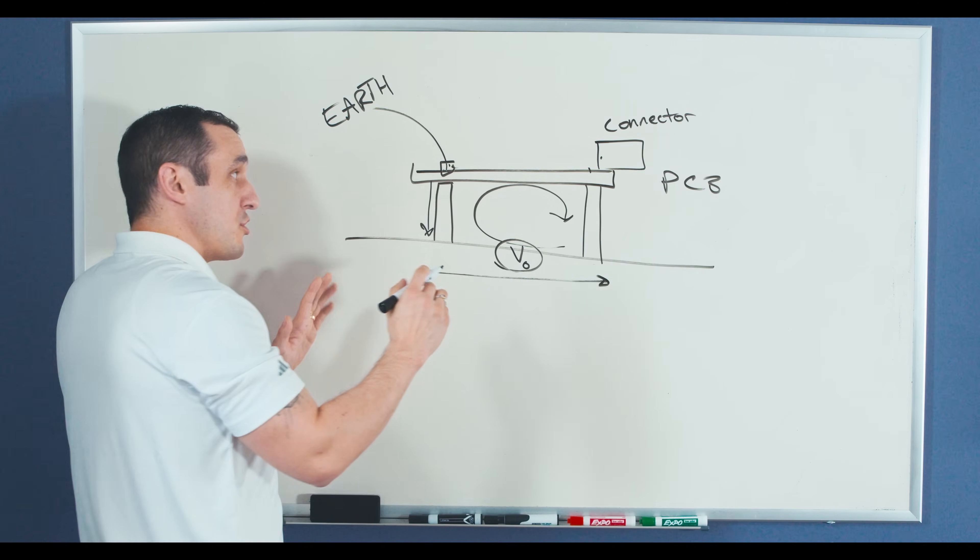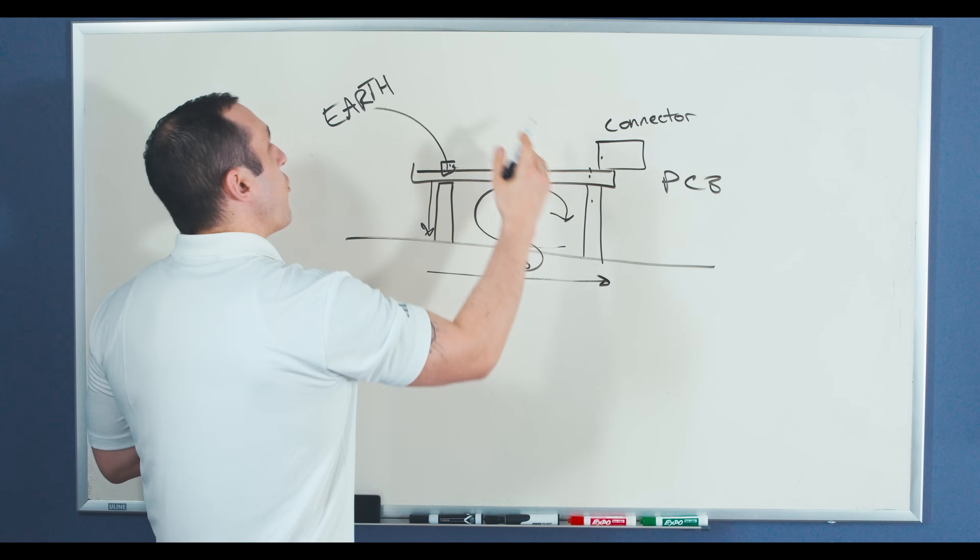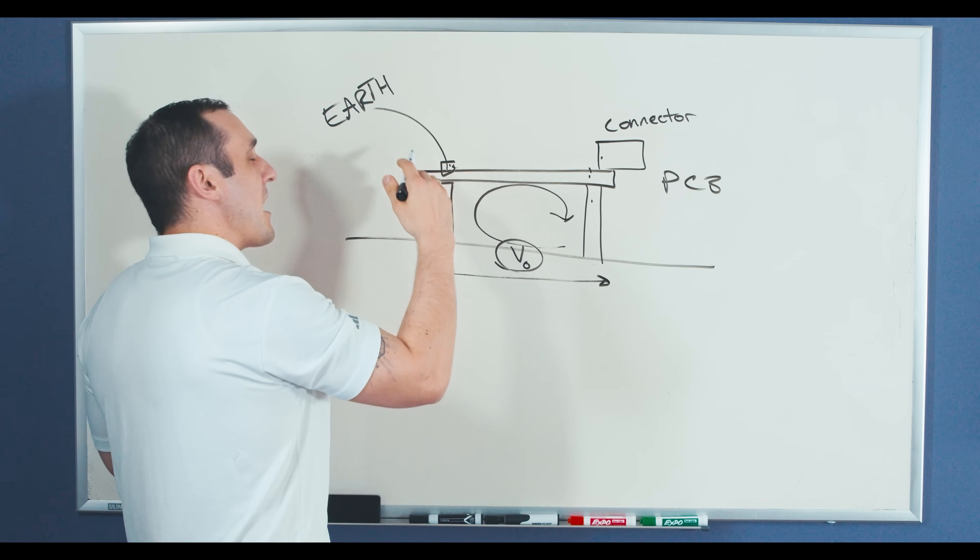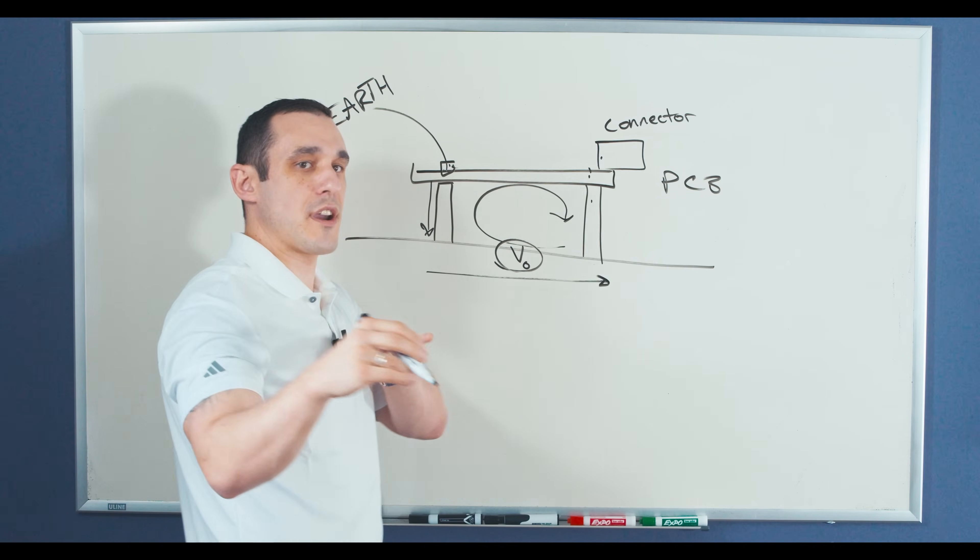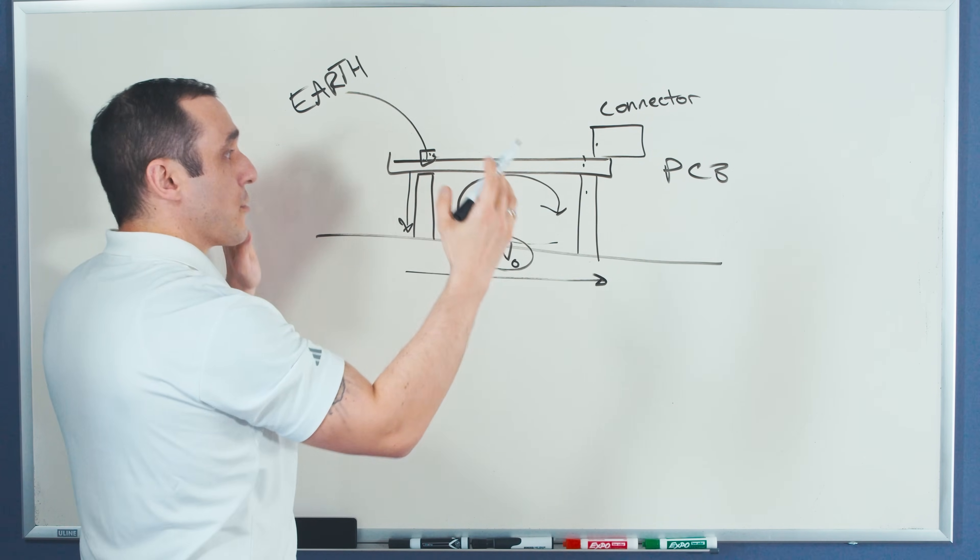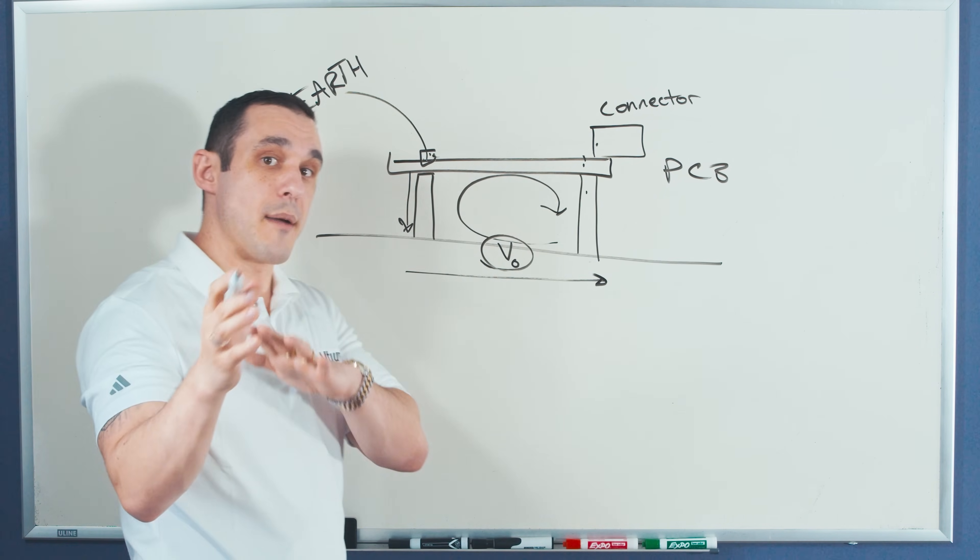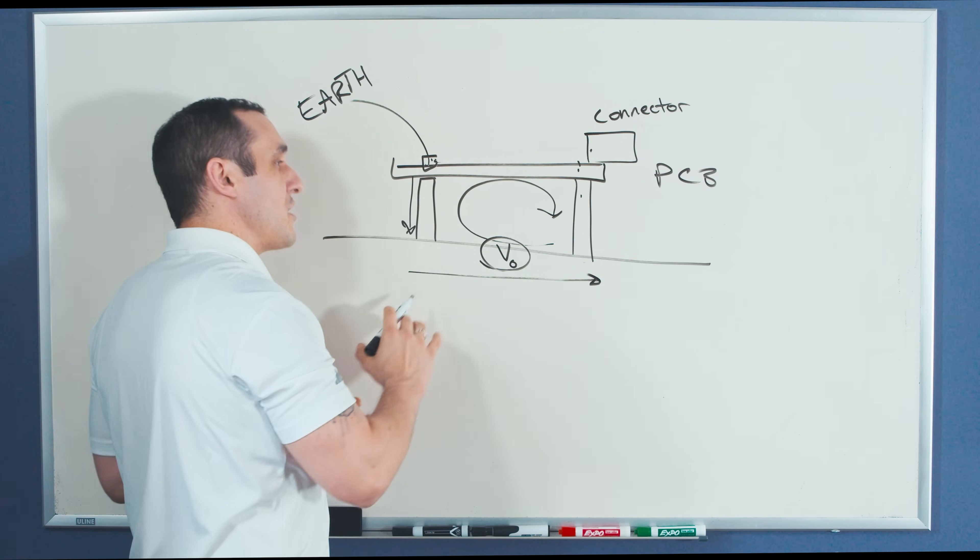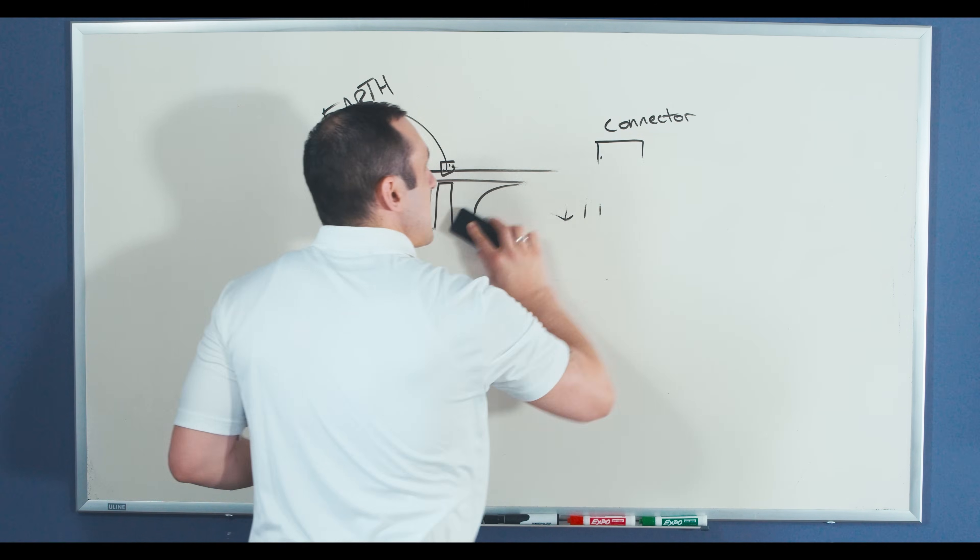For example, if you have a connector here with some shielding on the connector housing, all of that can be used to then access the safety ground. But again, because you're not putting a direct connection from here over to here, you're actually not creating a ground loop, even in this case where you have this connection among these different elements in a metalized enclosure. I think here the thing that you don't want to do is you don't want to connect your system ground over to your chassis ground when you have this earth connection. The issue here is that you could then run a current through that earth connection, and you end up then creating this loop of conductor here, which could then receive a stray magnetic field. So when you have that connection between system ground and earth, you're then running a return current through the metalized enclosure and through that earth connection. And remember, that's not the purpose of an earth connection. The purpose of an earth connection is to provide a safety ground for everything in this system.